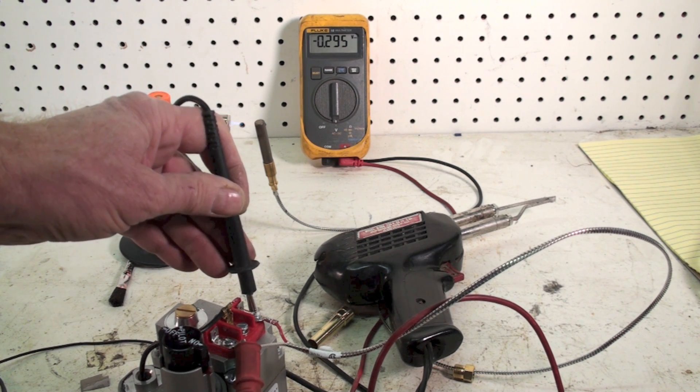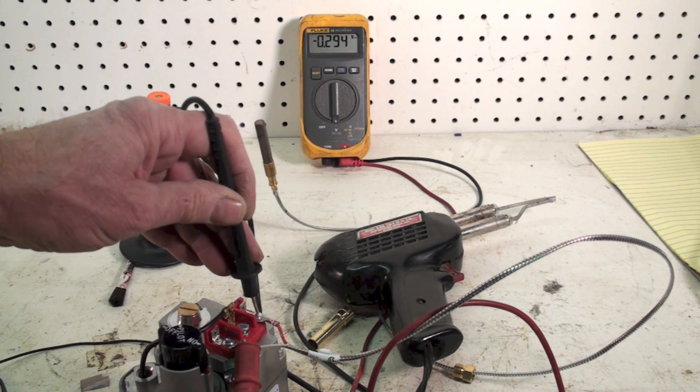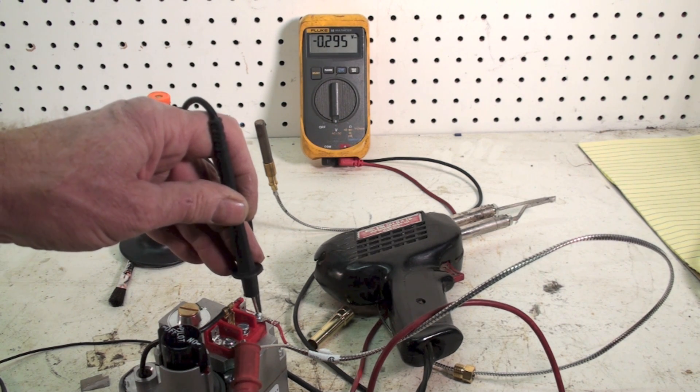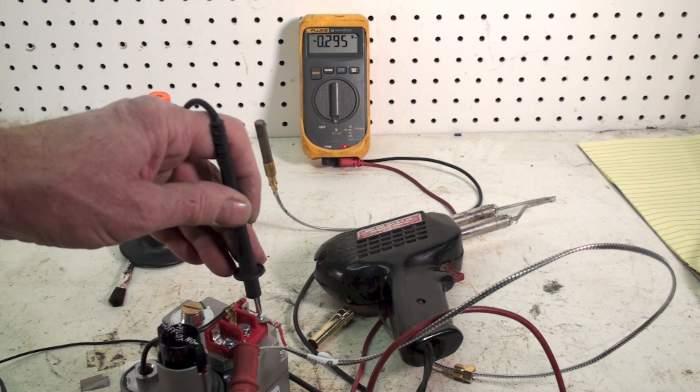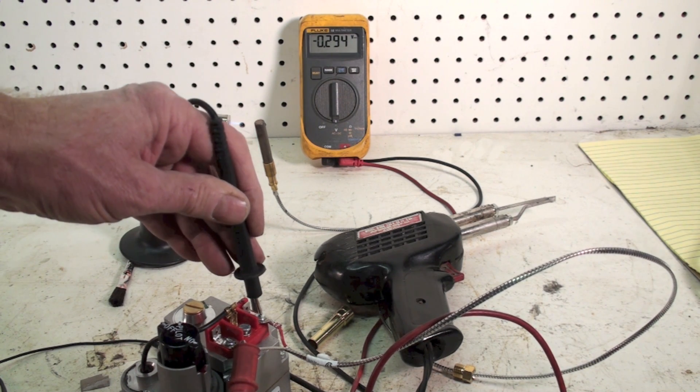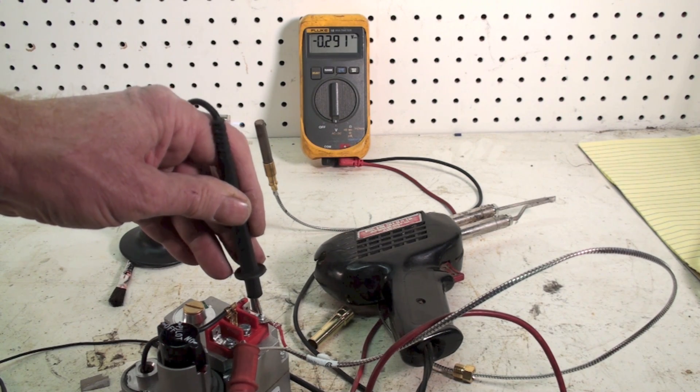I would expect 125 to 150 millivolts to energize the valve. That's closed circuit voltage. We're going to talk about how the gas valves are set up on these things and how the pilots are set up in another video.